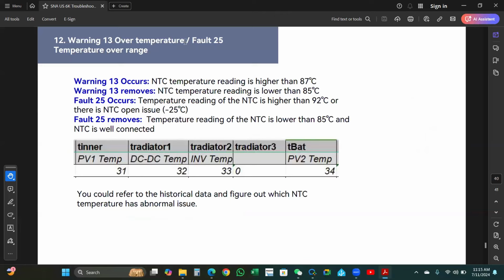Warning 13, over temperature, slash fault 25, temperature over range. Warning 13 occurs when the NTC temperature reading is higher than 87°C. Warning 13 removes when the NTC temperature reading is lower than 85°C. Fault 25 occurs when the temperature reading of the NTC is higher than 92°C, or there is an NTC open pin issue, which reads negative 25°C. Fault 25 removes when the temperature reading of the NTC is lower than 85°C and the NTC is well connected.